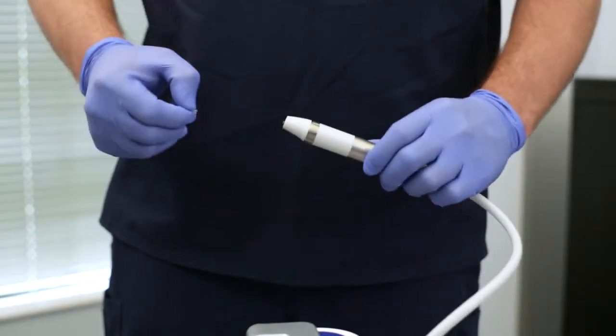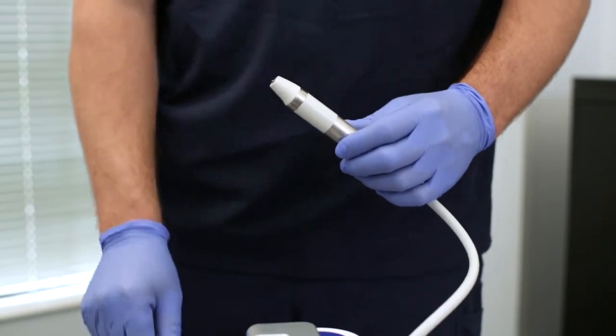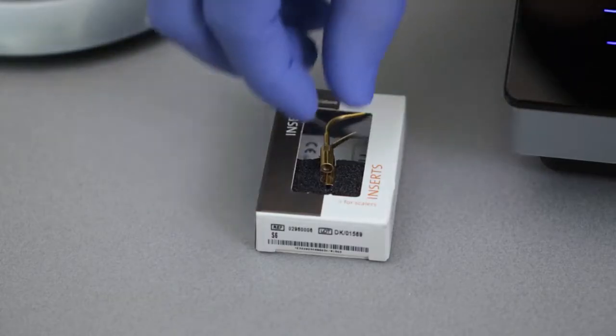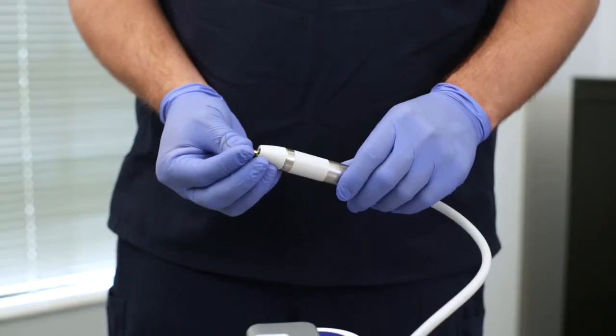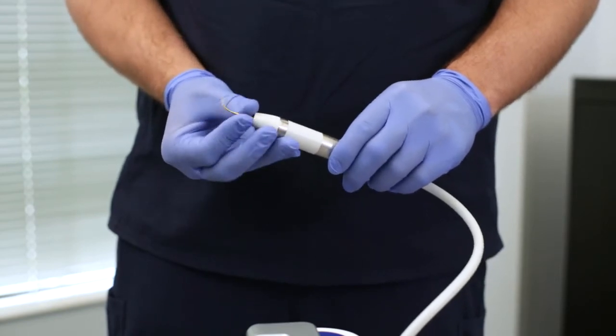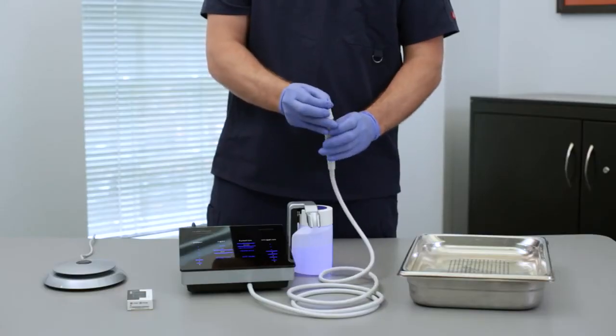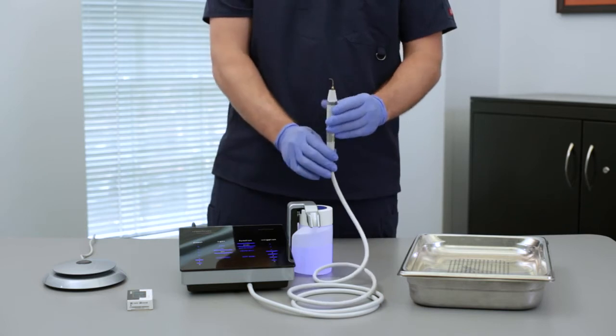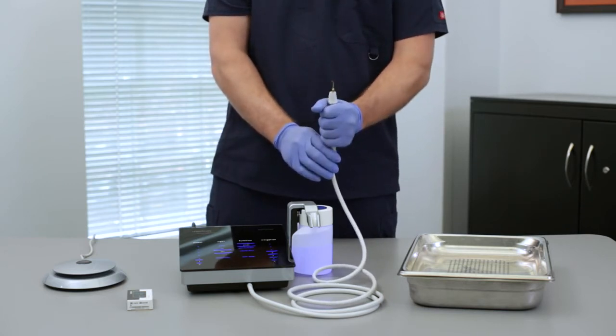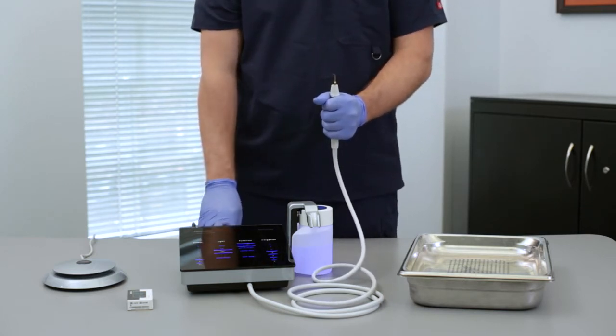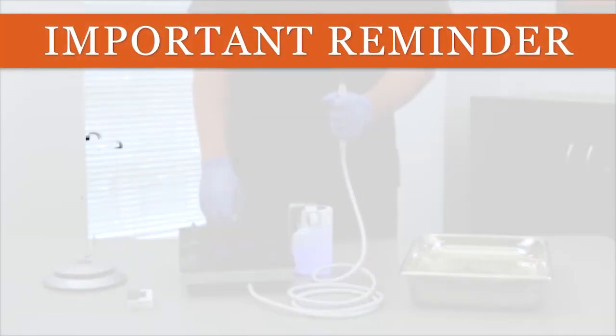Remove the clear plastic protecting the threaded portion at the tip of your handpiece and discard it. Take an insert tip and twist it onto these threads by hand until it stops. Hold the handpiece straight up with the insert tip pointed toward the ceiling, making sure that you are grasping both the lower and upper sections of the handpiece at the same time. This is very important, as repeatedly applying torque or pressure while holding in the middle or too low on the handpiece could compromise the handpiece itself or the connection to its cord.